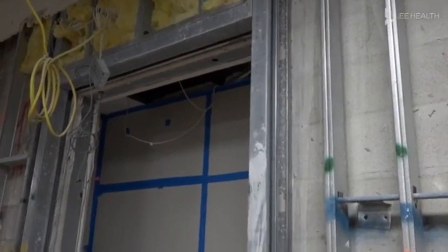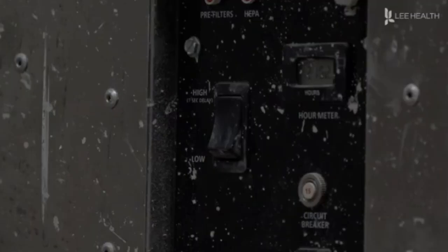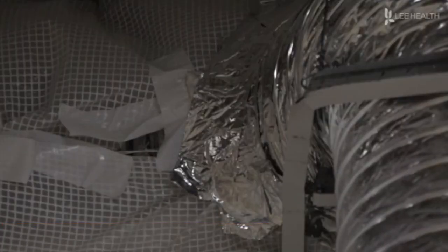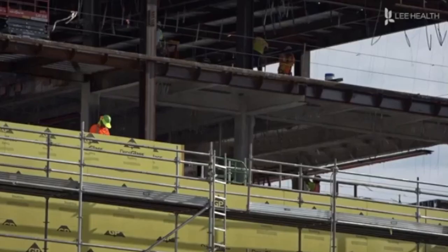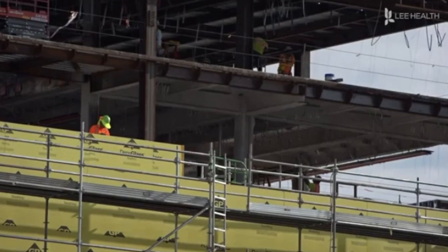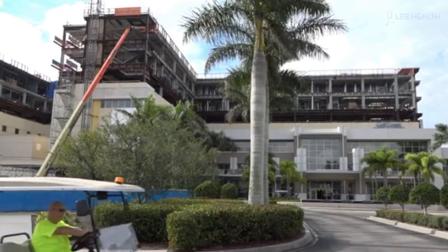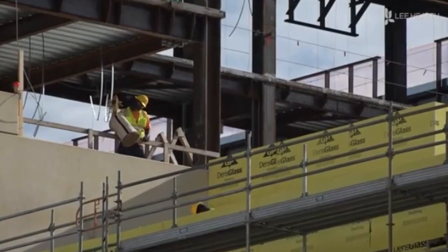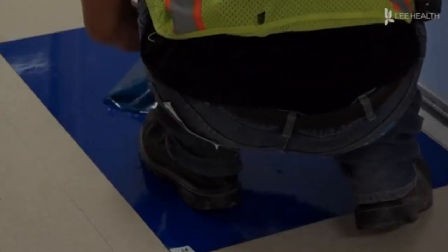You need to post signs identifying alternate exit areas. You need to inspect the exits that are affected daily to make sure there are no hazardous areas that are going to be overly dangerous. Provide temporary equivalent fire alarm and detection systems when the fire system is impaired. Use temporary construction partitions that are smoke tight and not combustible.